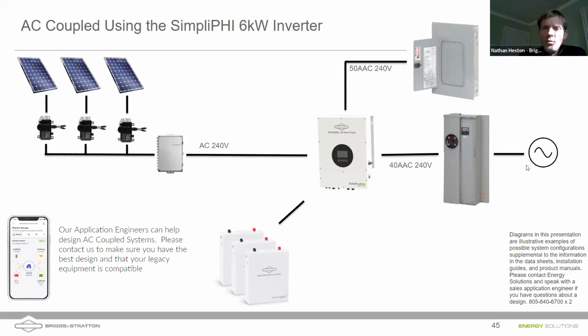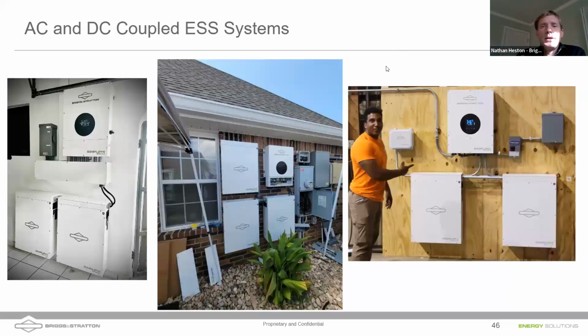So if the grid does go down, the batteries can supply essentially an island, a little microgrid, which will allow these microinverters to come back on and charge the battery bank, power loads, etc. in a grid down situation. That's normally something you don't have with microinverters and AC coupled systems. In a grid down situation, you don't have solar power. Well, add even a small battery bank and you can keep that solar power pumping.